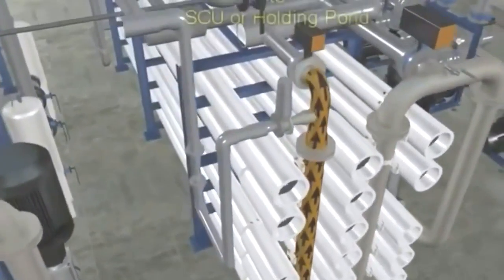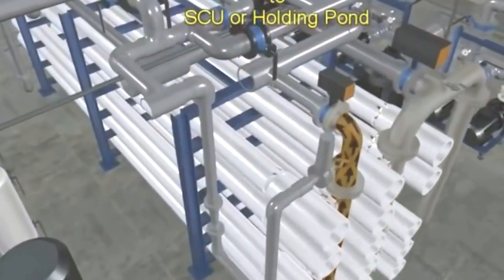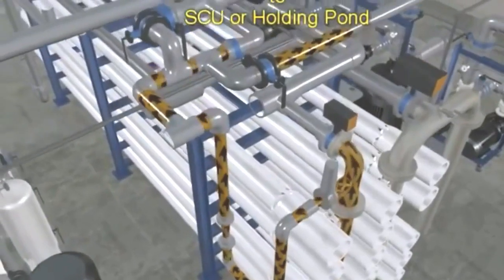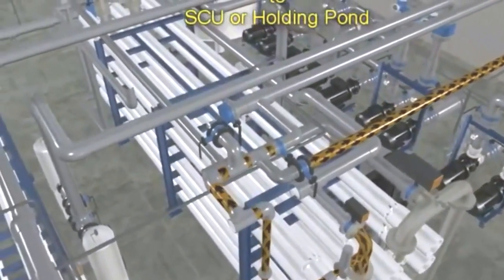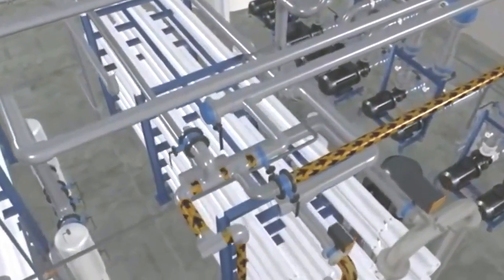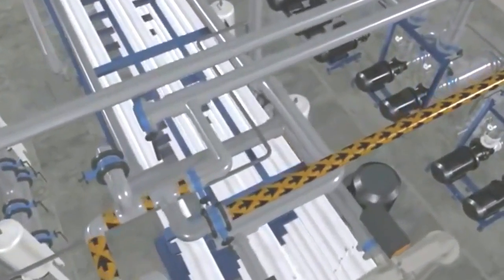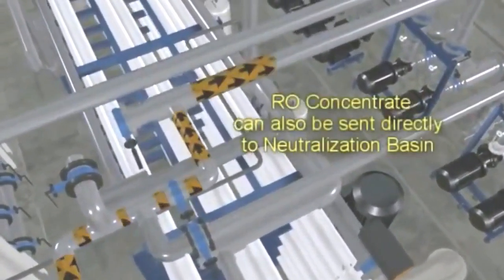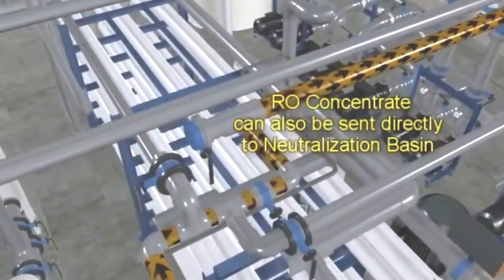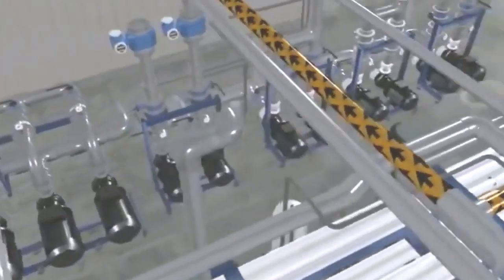This concentrate can be directed to the discharge water tank, where it can then be transferred to the solid contact unit, or holding pond. Concentrate from the RO can also be sent directly to the neutralization basin, which normally occurs when concentrate is collected during RO cleaning or UF cleaning.